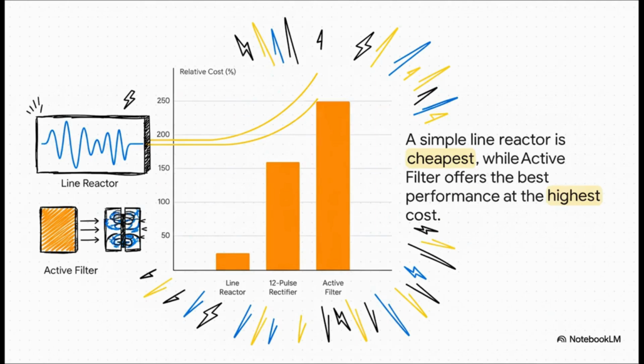But of course, every engineering decision is a trade-off, right? That simple line reactor is by far the cheapest option. If you move up to more advanced solutions like 12-pulse rectifiers or especially those active filters, you're going to get even better performance, but you're also going to pay a significantly higher price. The right choice always depends on what the application actually needs.